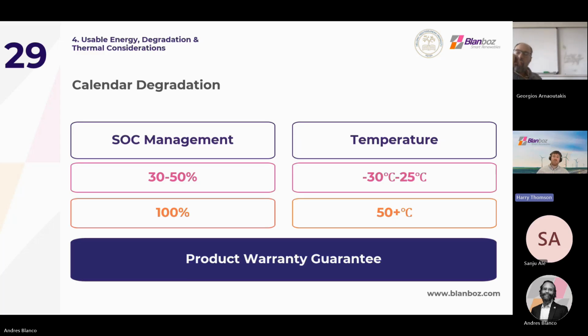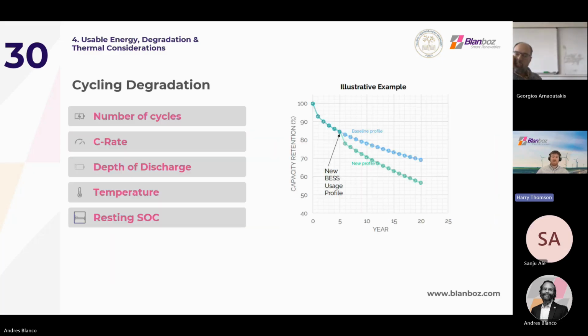We'll now look through the 5 primary factors for cycling degradation, or degradation through use. So first of all, we have the number of cycles. More cycles means more cumulative damage with each charge and discharge cycle. In the UK, for projects, we see this ranging from an average of 1 to 2 cycles per day. C rate: the higher the C rate, the more accelerated the degradation. This is because the BESS is working harder and under more stress to discharge faster.